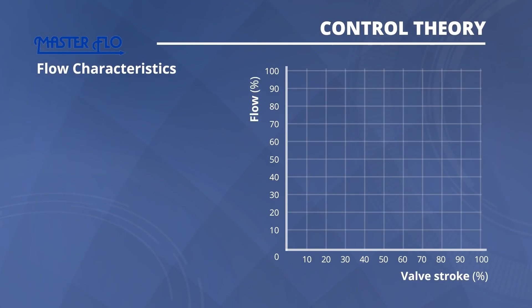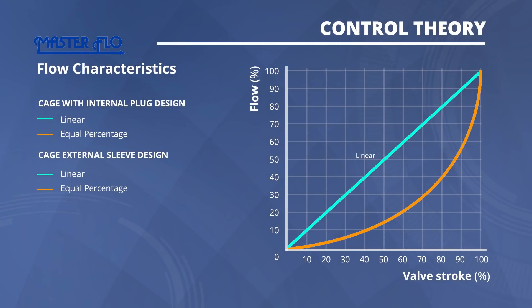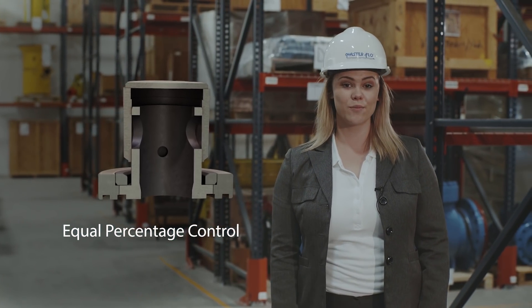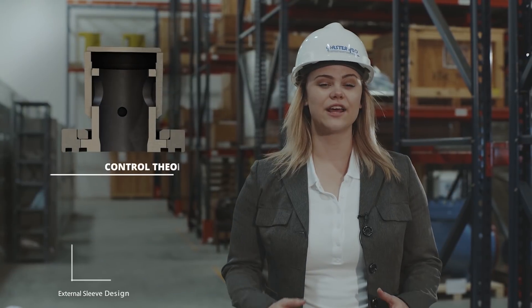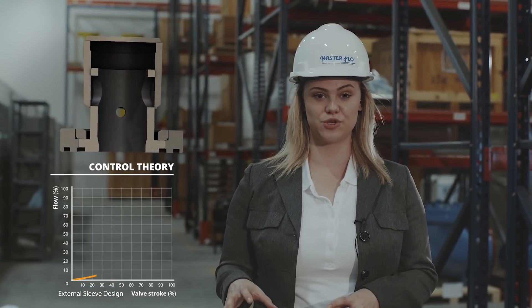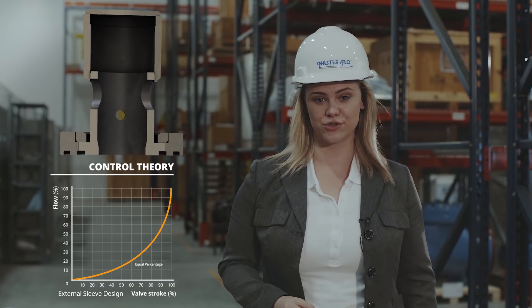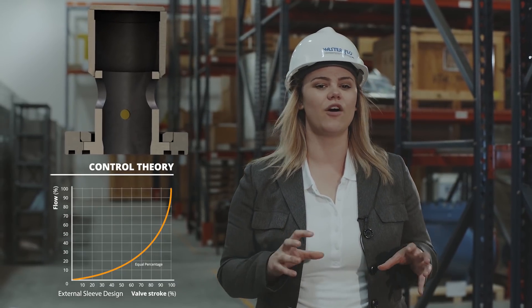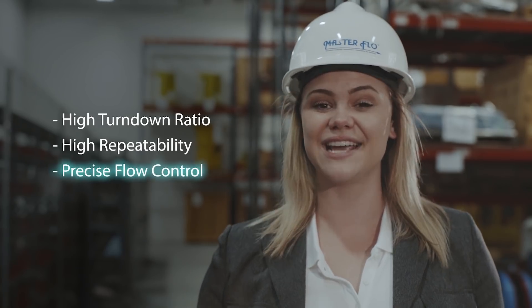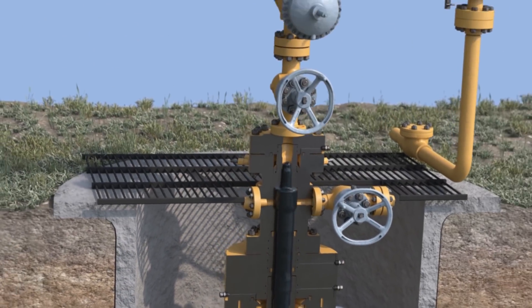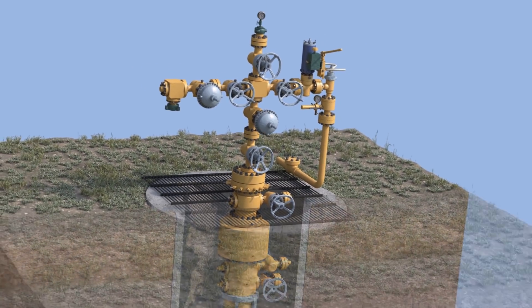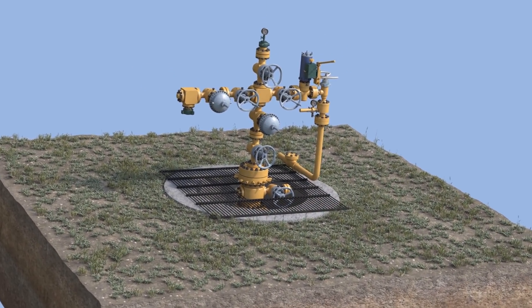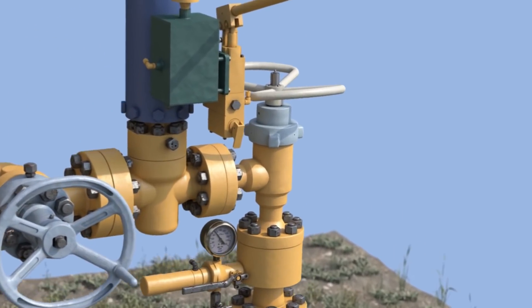The cage with internal plug and external sleeve choke valve designs are both characterized by equal percentage or modified parabolic control. They provide a gradual response in the lower portion of stem travel, delivering a high level of initial control. This brings the well on stream. As the valve is open and the flow increases, this level of control is maintained throughout the stem travel, resulting in high turndown ratio, high repeatability, and precise flow control.